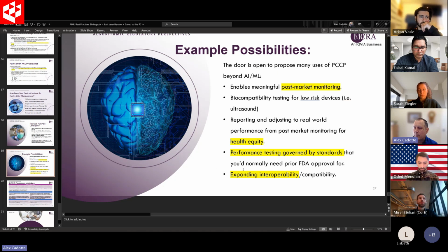A lot of these are aspirational in terms of different things. If you're going to be doing a PCCP, you're going to have to be monitoring the performance of your device in the post-market. There's no way around it. It does enable meaningful post-market monitoring. FDA thinks that's the best practice anyway, to make sure you understand how your device is performing in the field. Other possibilities are biocompatibility for low-risk devices, for example, ultrasound probes, and adjusting to real-world performance. I'd put this in as an aspirational thing for health equity. We tried it with FDA and it didn't work, so I have to take that one back.